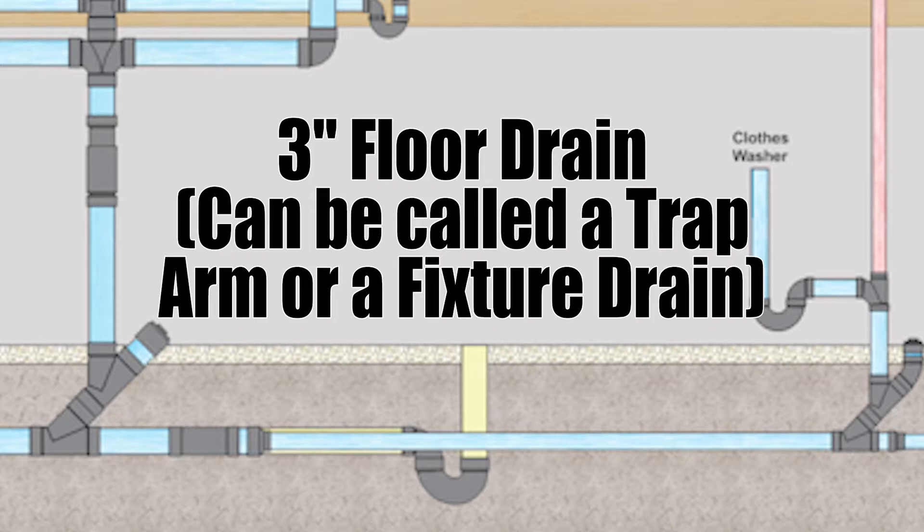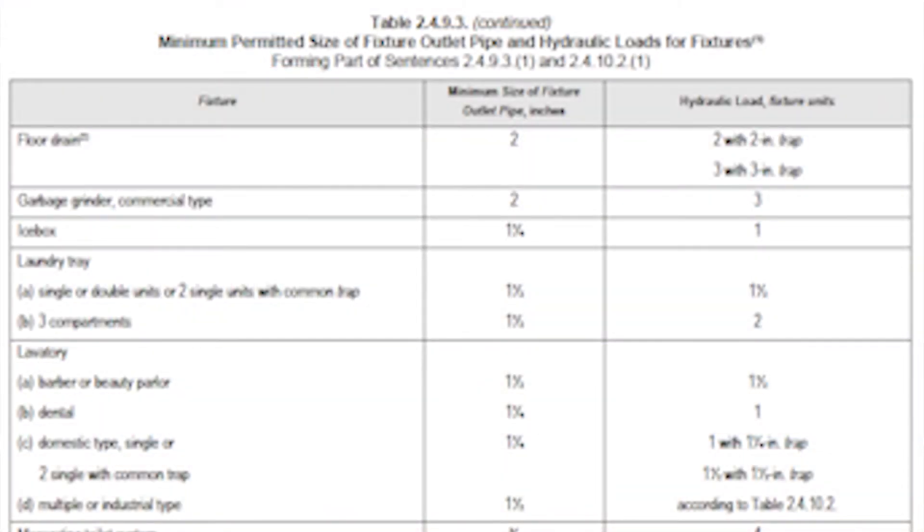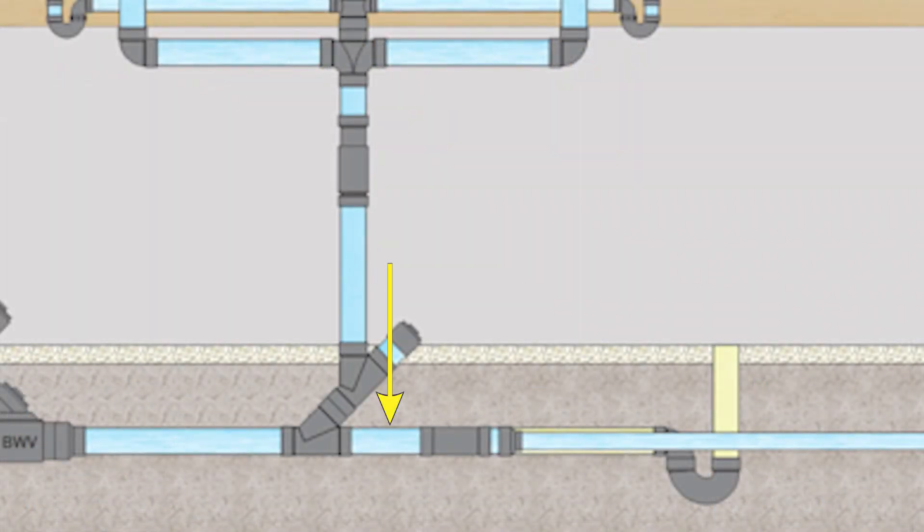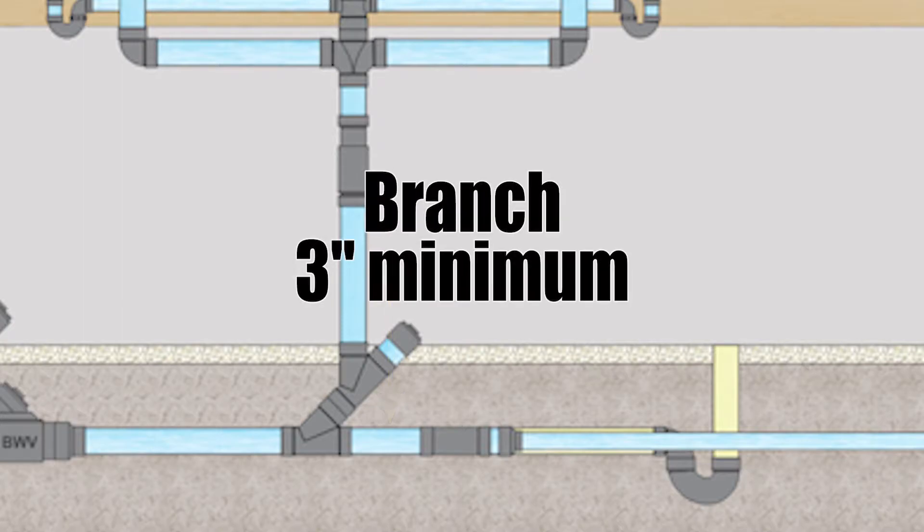That will be discussed in a future video but just so we know table 2.4.9.3 says that a floor drain can actually be two inches in size. So it would be two fixture units with a two inch trap or three fixture units with a three inch trap. And now we've got another small length of horizontal pipe that is the junction of two or more soil waste pipes therefore that is a branch as well. Now we're serving a three inch floor drain therefore that branch will need to be three inches.